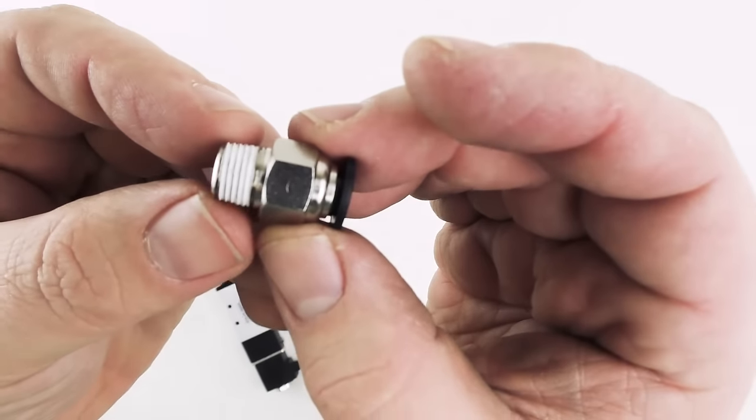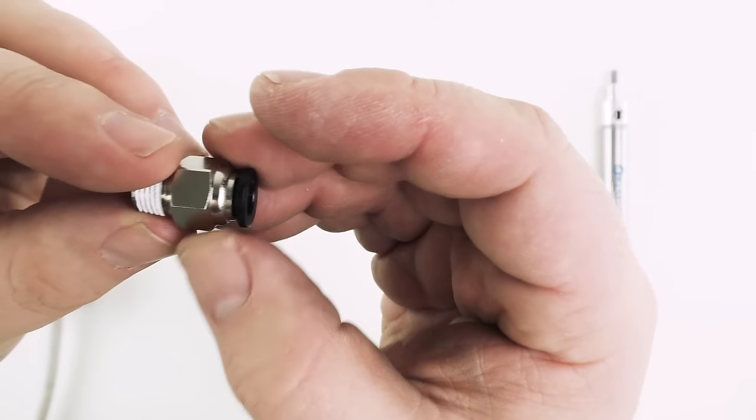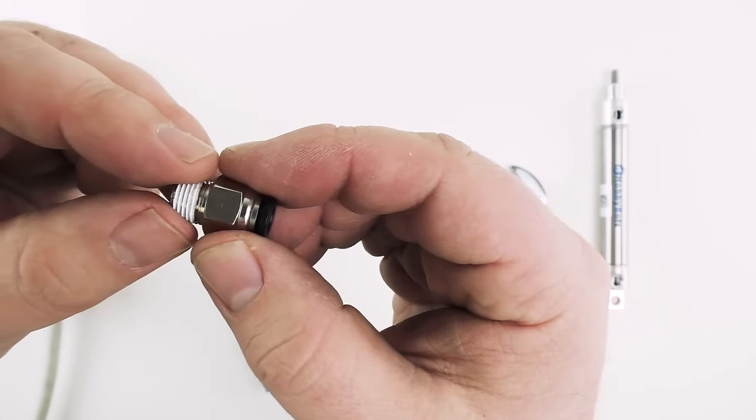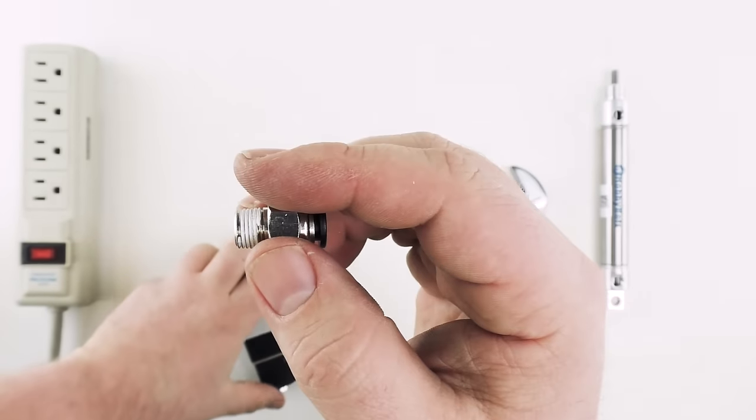You can see here that these fittings already have some Teflon applied, that's that white you see around the threads. If you find that after you tighten your fittings in there's still air leaking you may want to apply some additional Teflon tape to the fitting and then reinsert it into the solenoid and tighten it back down.